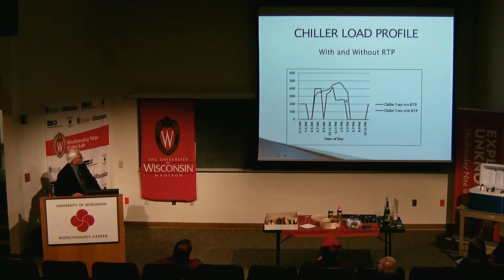Now here is the chiller load profile. The blue line indicates the chiller load before he enrolled in the RTP program, and the red line indicates after enrolling in the RTP program. The difference is the energy savings and thereby energy cost savings also. You can see that there is load here because you are making ice in the off-peak period.